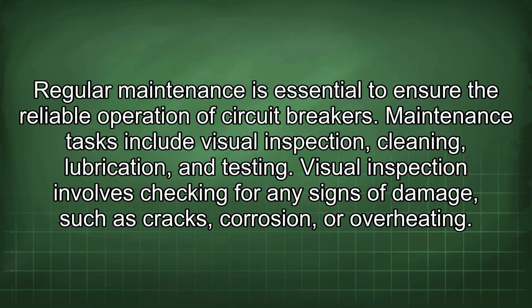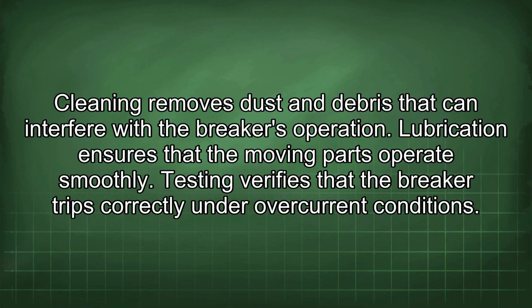Regular maintenance is essential to ensure the reliable operation of circuit breakers. Maintenance tasks include visual inspection, cleaning, lubrication, and testing. Visual inspection involves checking for any signs of damage, such as cracks, corrosion, or overheating. Cleaning removes dust and debris that can interfere with the breaker's operation. Lubrication ensures that the moving parts operate smoothly. Testing verifies that the breaker trips correctly under overcurrent conditions.